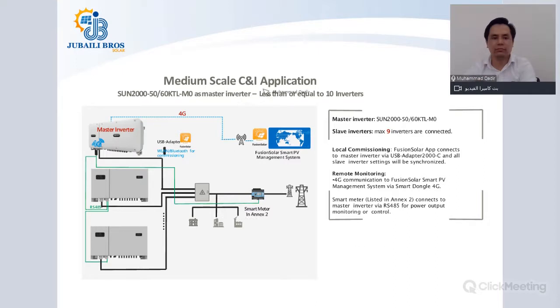Medium scale C&I application. In this scenario, the master inverter is the 50 or 60 KTL, and again we are using either 10 inverters or less. Here, if you are using the 50 or 60 KTL, you can connect a dongle, but the only choice is the 4G dongle, because the 50 and 60 are compatible only with the 4G dongle. Again, a maximum of 9 slave inverters can be connected.